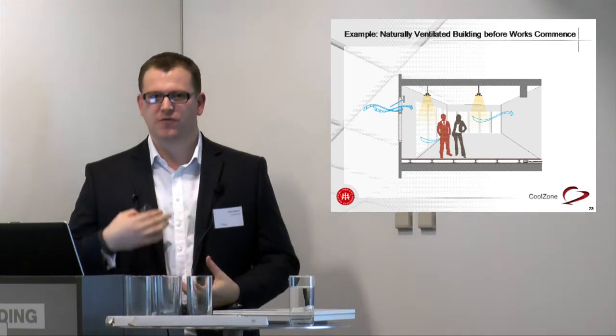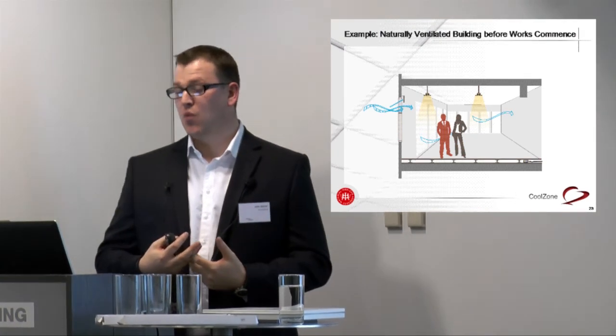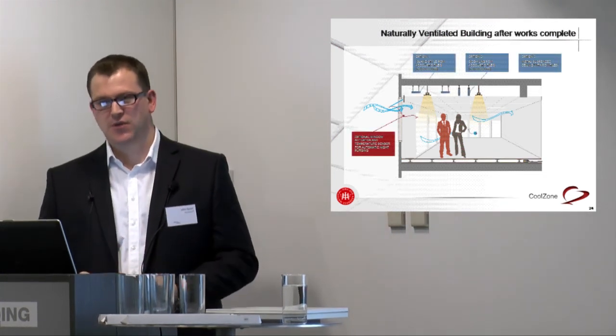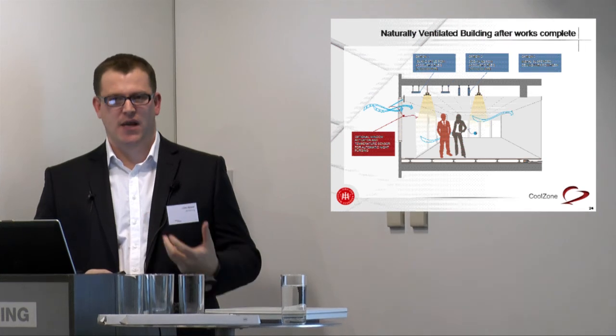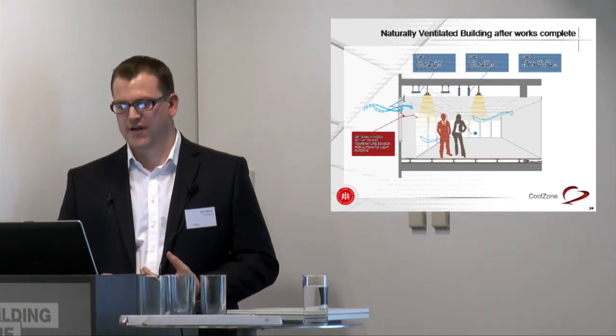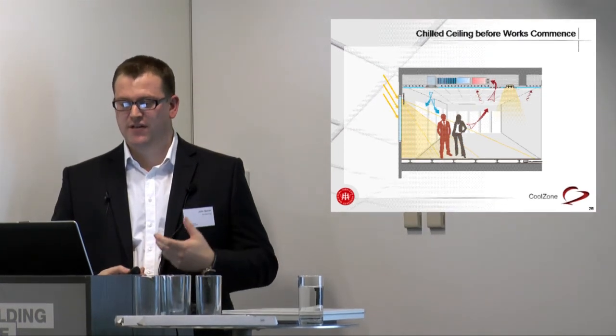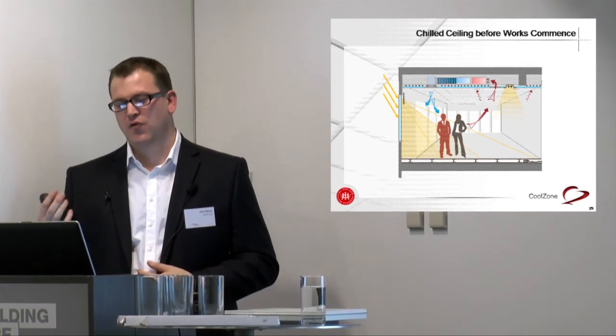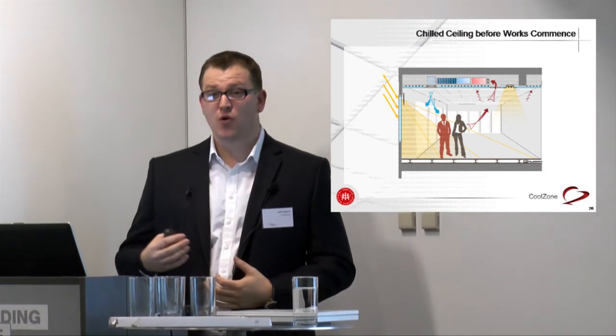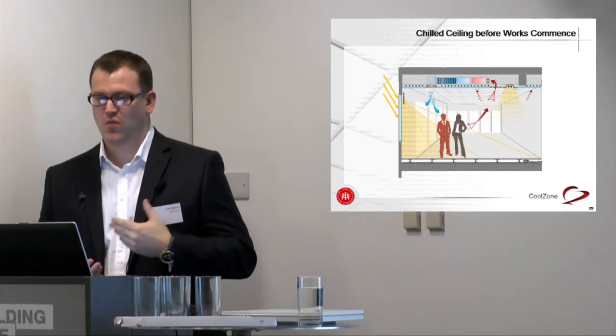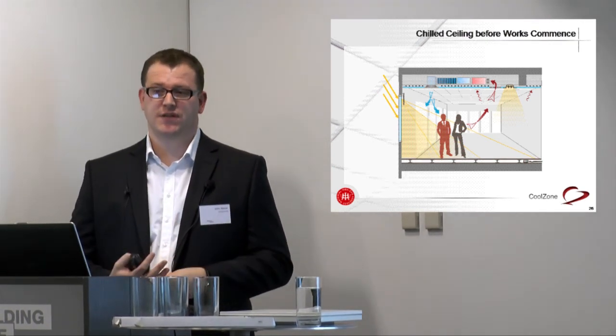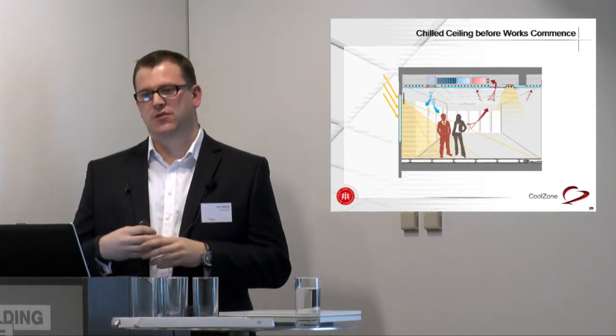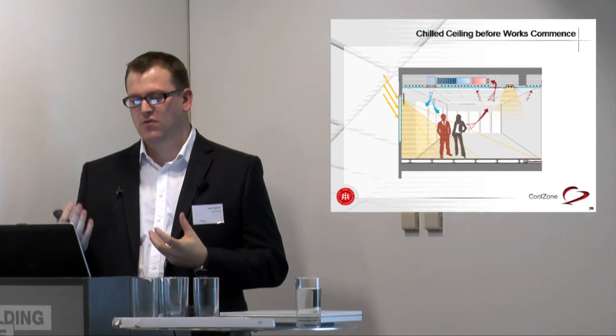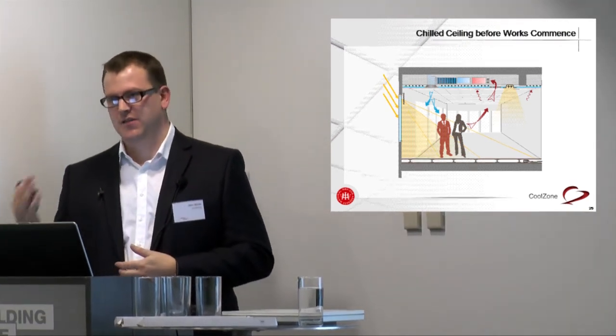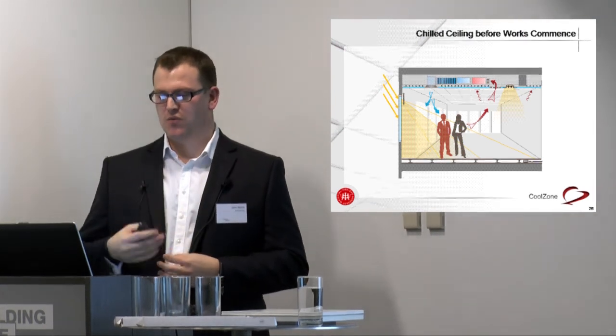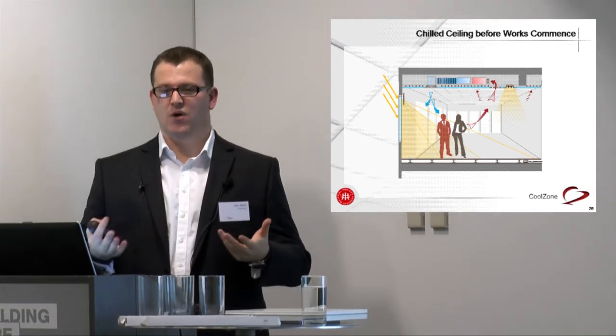These are some examples of what you'd need to do to make the cool zone work and get that purge. For a naturally ventilated building it's very easy: we add the PCM, whether as a canopy, a baffle or a ceiling, and all we have to do is open the window to get the purge. For a chilled ceiling, generally they're quite efficient to start with, and we have a business in Switzerland that makes chilled ceilings. We're looking to add the PCM into the chilled ceiling so you have an active solution, so we don't rely on whether we can get a purge or ventilation. We have a system you just put in place and it works every time.